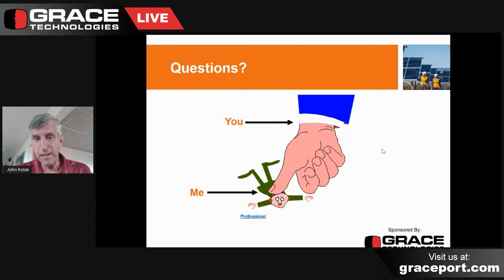So we're not just modeling it because it's in the system. It's not going to be over duty if it's just continuous current normally. Although I suppose it's possible if they've engineered a bus bar such that there's more fault current there than the device can handle just for conducting current, well, then you'd melt the device. But normally speaking, the reason we don't worry about switches is that they're not interrupting current flow. They're just conducting it. And when you'd operate the switch, it would normally be for routine switching. You wouldn't be doing the switching under fault duty. I hope that helped the person who asked the question.